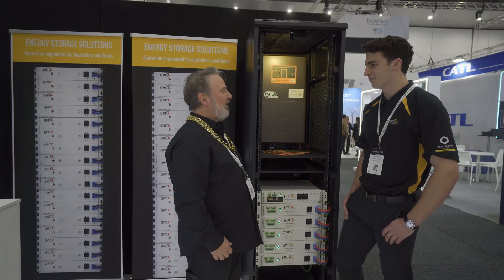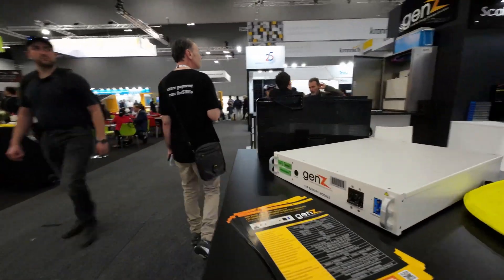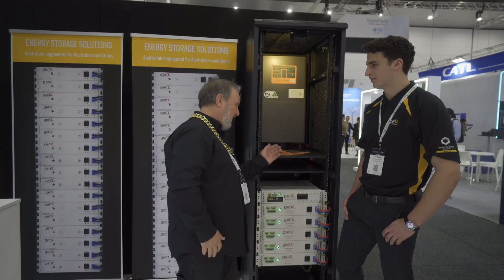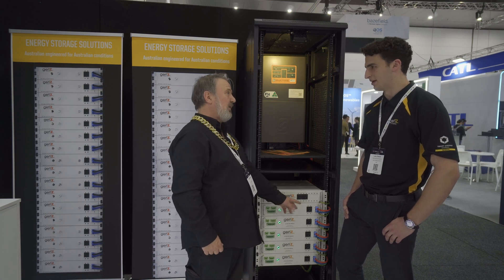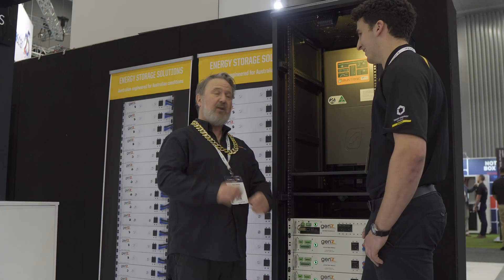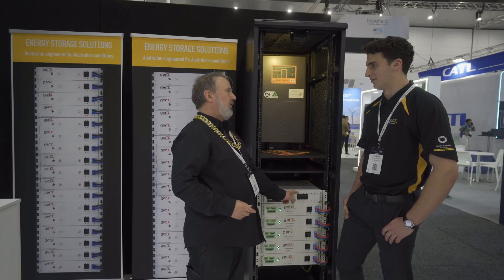That's the holy trinity. Because I get this question a lot when people see multiple battery modules — they ask, do I need a single isolator somewhere upstream? Well, if every single inbuilt isolator meets that requirement, no you don't. But it's a lot of switches to turn off, and you've got to have all that on the shutdown procedure. Now you've got a single point of isolation.